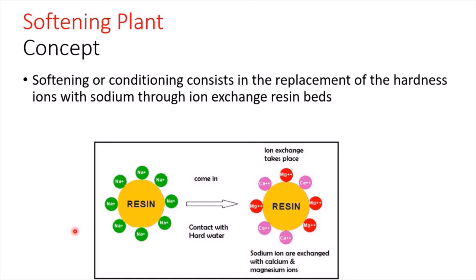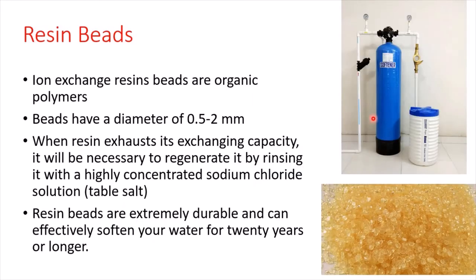Softening consists of replacing the hardness ions — calcium and magnesium — with sodium ions. We have a certain media called resin, and on this media there are sodium ions. When the resin comes into contact with hard water, the sodium ions are exchanged with the calcium and magnesium ions. Our water will no longer contain calcium and magnesium, but will contain sodium ions instead. This is what we call the ion exchange process.